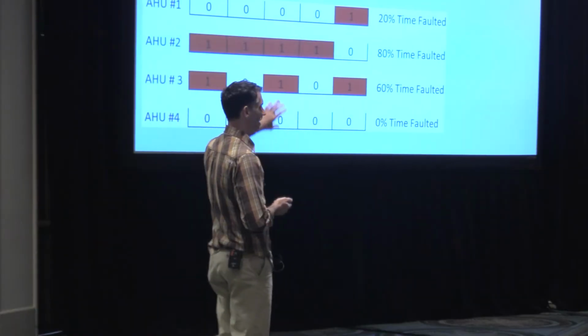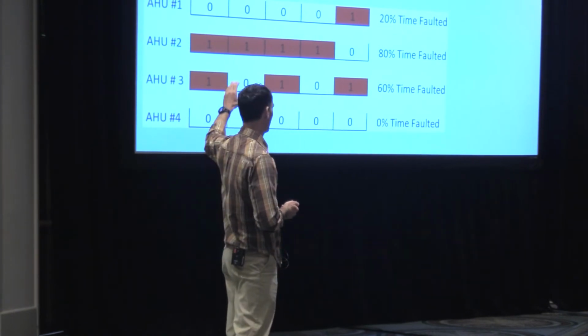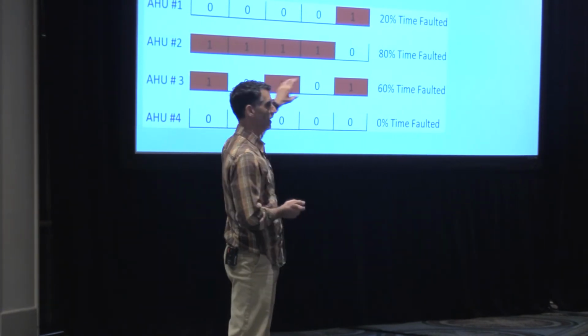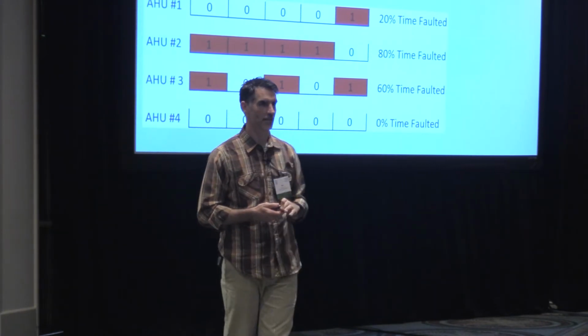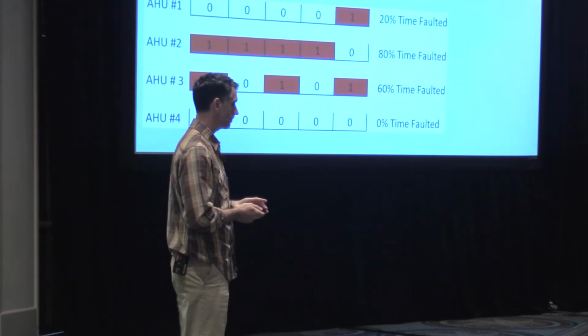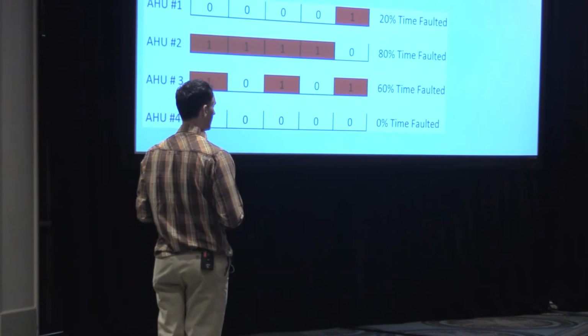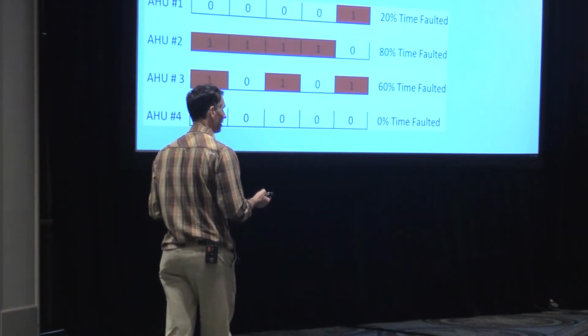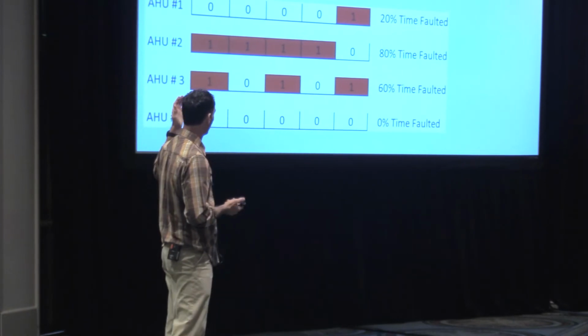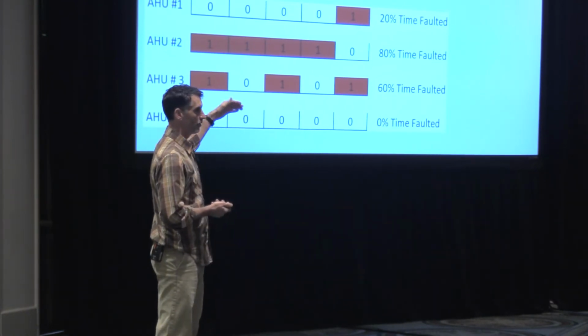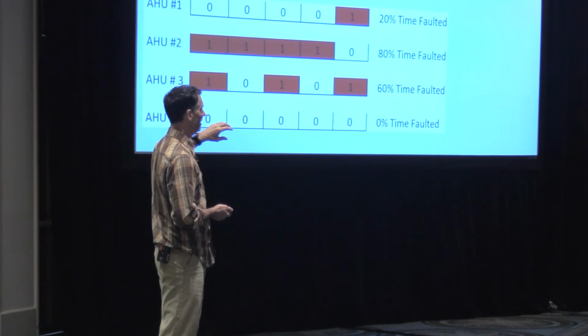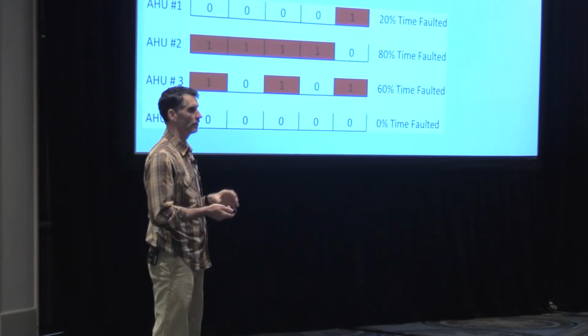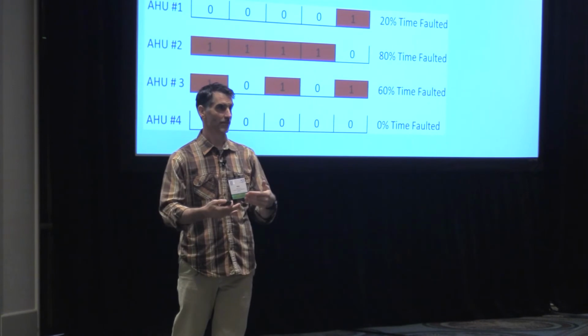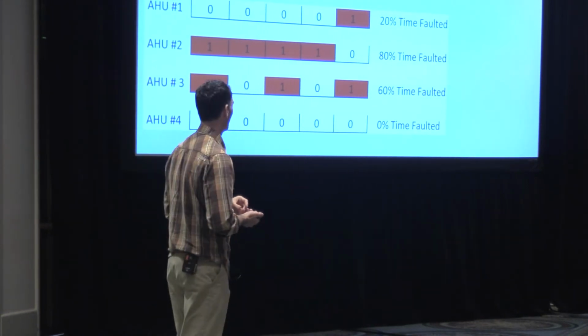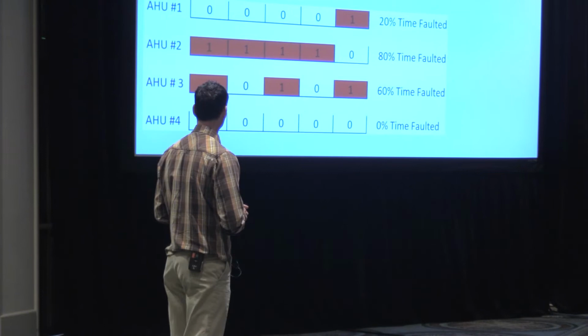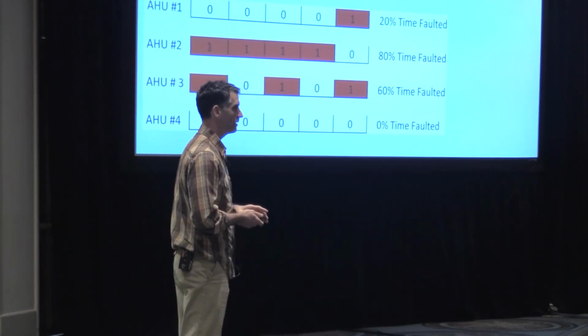Hypothetically, if this was our whole data set, we've got 4 air handlers and 5 days worth of data. Of course, our actual data set is a lot bigger, but just to illustrate the point: if we picked a specific fault, mixed air temperature abnormal, and found that for air handler 1 it was fault-free for 4 days, then the fault occurred on the 5th day, that air handler had the presence of the fault 20% of the time. For air handler 2, it's faulted 80% of the time, and so on.